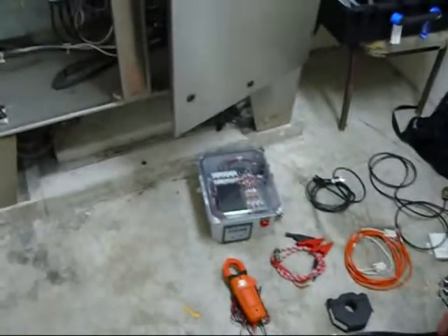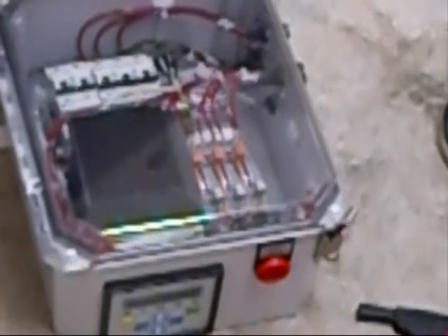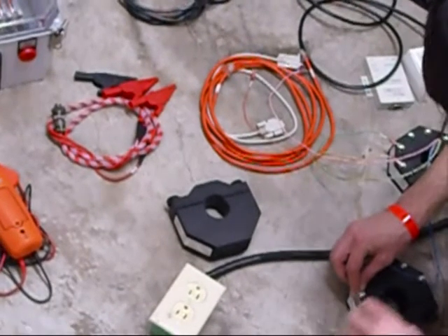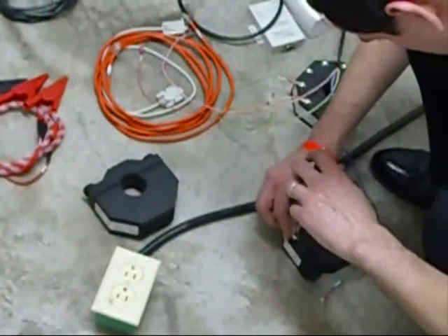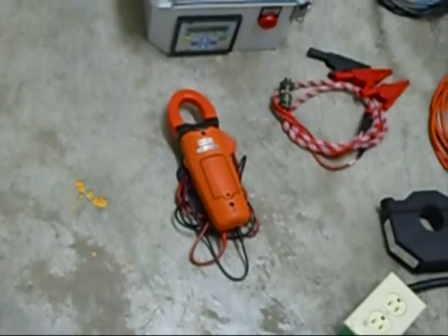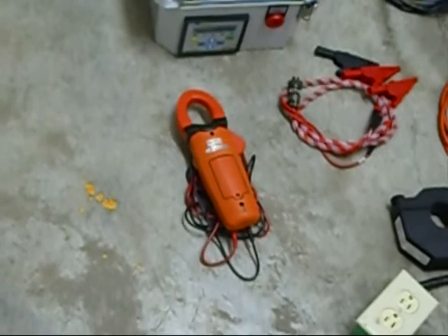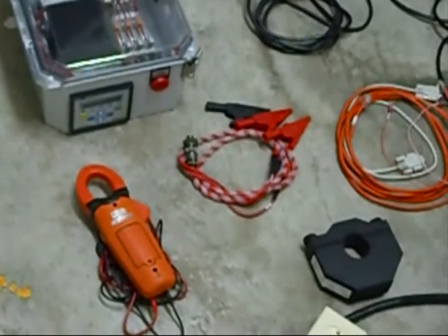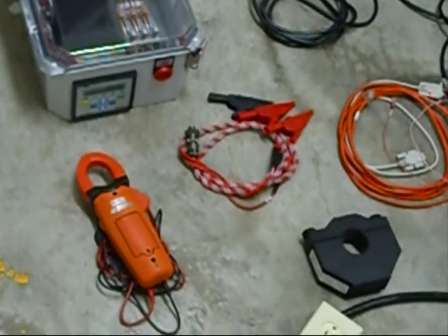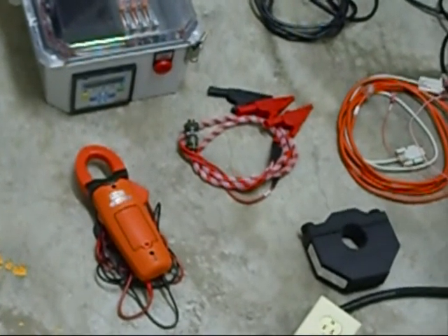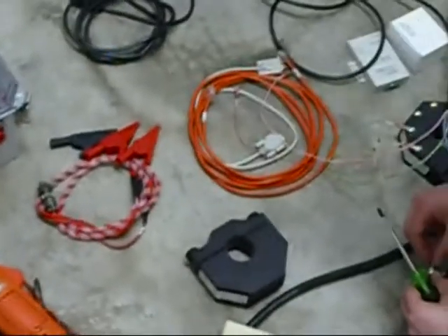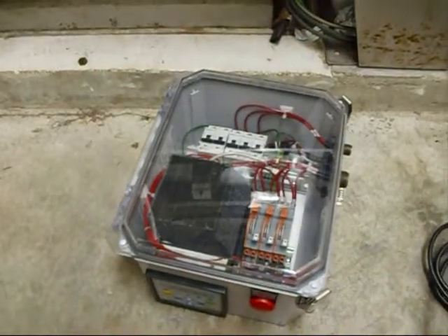So in the box over here we have the MCM unit fitted with the appropriate circuit breakers and fuses and so on. And over here we have split core current transformers. Joe here is just pre-wiring a couple of those, and we've got the tools that you require to go with it. So a snap-on ammeter and voltmeter, cables with crocodile clips or alligator clips if you're based over here, and communications cables. There you go.